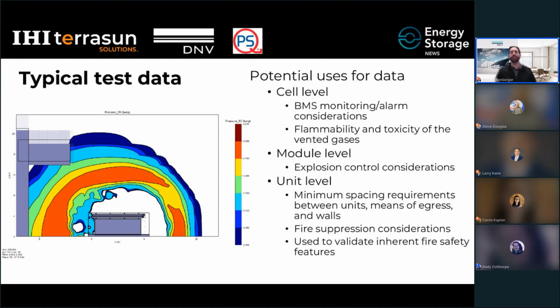From the cell level tests, cell vent gas composition also plays an important role in being able to evaluate the fire and explosion hazards posed by a particular system. So gas compositions and further on gas volumes from the module level tests let us run simulations to be able to evaluate the effectiveness of both explosion and fire controls within the BESS enclosures. At the module level, in the 4th edition of UL9540A, where thermal runaway propagation is required to be observed, this can give us an idea of the volume of gas that's generated within the enclosure unit.